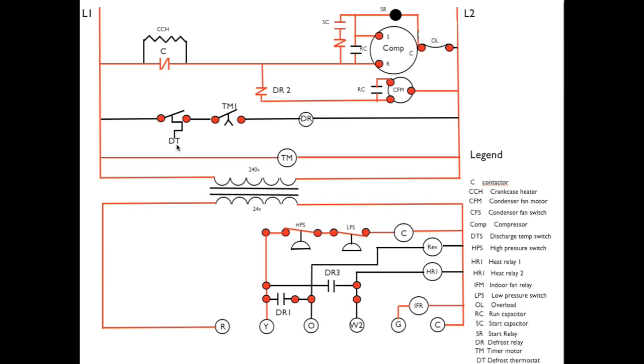The defrost thermostat is mounted on the outdoor coil. It has to be below a certain temperature of 32 or 26 degrees. Both of these have to be closed to energize the defrost relay.